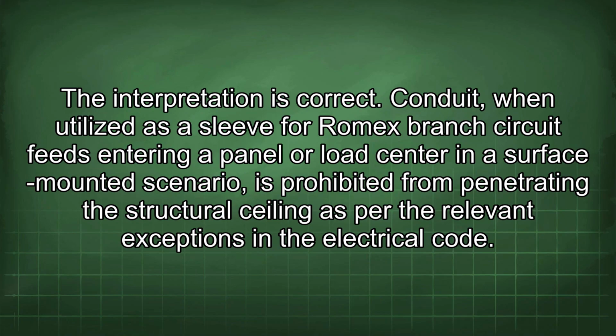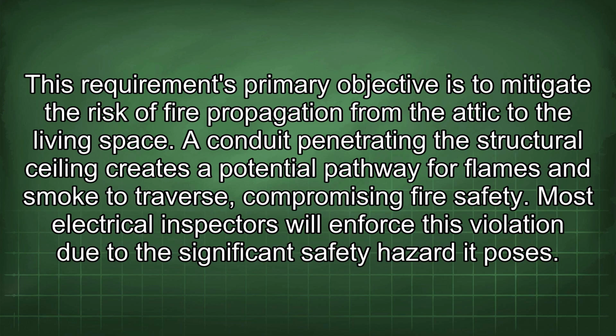The interpretation is correct. Conduit, when utilized as a sleeve for Romex branch circuit feeds entering a panel or load center in a surface-mounted scenario, is prohibited from penetrating the structural ceiling as per the relevant exceptions in the electrical code. This requirement's primary objective is to mitigate the risk of fire propagation from the attic to the living space. A conduit penetrating the structural ceiling creates a potential pathway for flames and smoke to traverse, compromising fire safety.